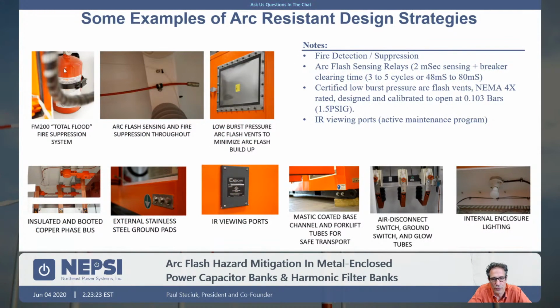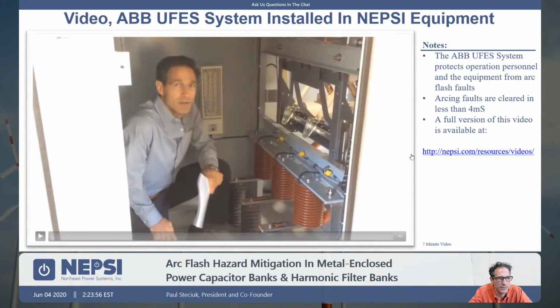So we won't go through all these in detail, but this is just some examples of the type of technologies we use. This arc blast vent is another interesting concept. It's an arc blast vent that's got a certified blast rating to it. In this case, it's 1.5 pounds per square inch. We include these on some of our enclosures where arc flash hazard is being strongly considered. The burst vent allows for the expulsion of gases outside the enclosure should there be buildup inside, and it's a certified pressure value.